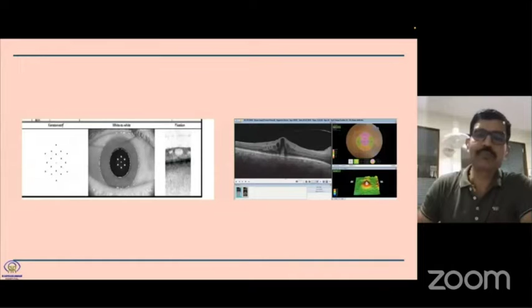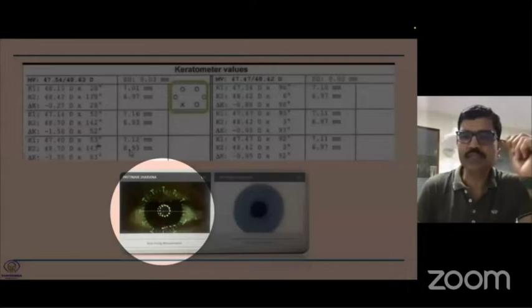Out of these three technologies and the modern day machines, let's look at the reliability indicators. Where are they? The modern day machines have these keratometry printouts where, if the mires have not been properly taken, the machine cross marks them. You can also look at the mires yourself on the cornea to see whether the reflection has been proper or not, to know whether it's reliable.